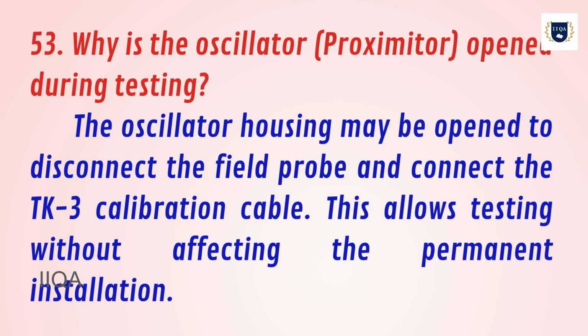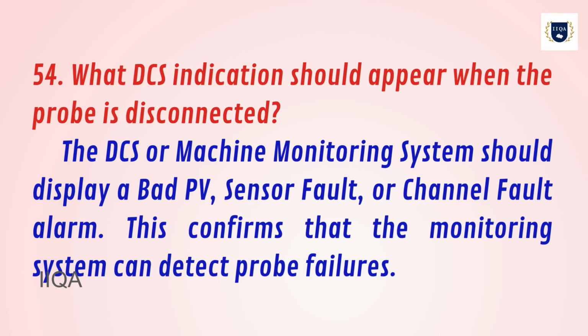53. Why is the oscillator, Proximitor, opened during testing? The oscillator housing may be opened to disconnect the field probe and connect the TK3 calibration cable. This allows testing without affecting the permanent installation.